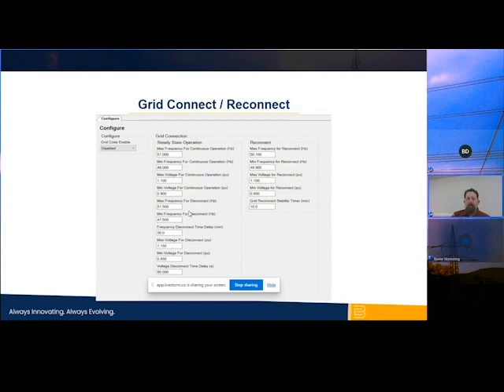So I set my frequencies, and then I set my max frequencies, and then I will set my time delays. You'll notice those time delays in these are in minutes and seconds, so they're long time delays. And also, if you look at the right here, likewise, we're going to set those conditions. So when the grid conditions recover, or they get back within our thresholds of frequency, now we're going to say, okay, we're ready to reconnect.